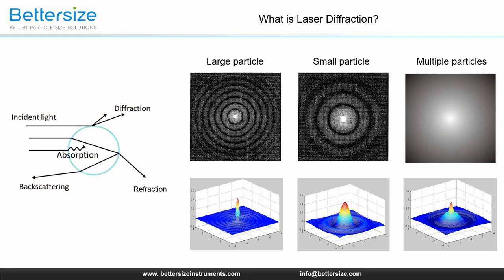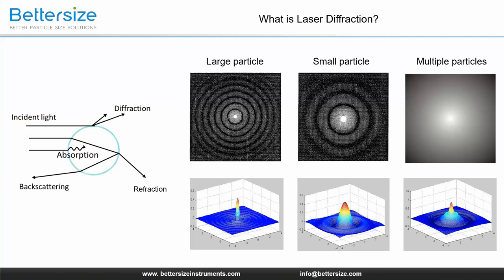What is laser diffraction? Laser light is coherent and almost monochromatic — it consists of light of one wavelength. If it hits a particle, then depending on the size of this particle, different physical effects occur, including refraction when passing through a surface boundary, diffraction at a particle with a diameter significantly greater than the wavelength of the light, and light scattering at a particle in the size range of the wavelength or below, in which an interaction with electrons takes place. Laser diffraction as a particle size measurement method is based on the diffraction of light at particles that are much larger than the light's wavelength.